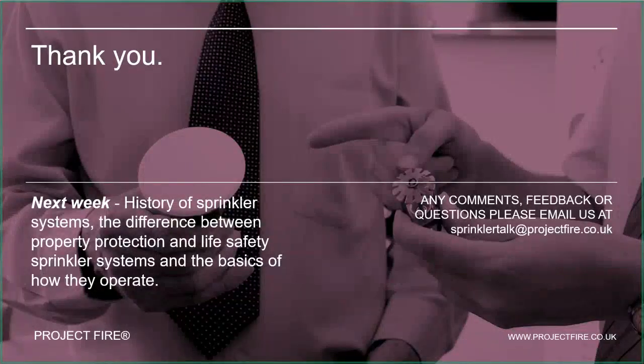Or you can use a different type of sprinkler system entirely, such as a dry system or dry pipe system where there isn't water permanently in the pipes, which also solves the problem. If you come across a system with freezing issues, definitely contact a sprinkler servicing contractor, and they can advise whether to go for lagging or a trace heating system.